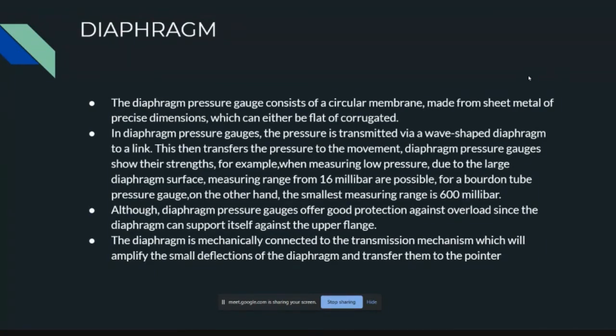Diaphragm pressure gauges show their strength, for example, when measuring low pressure. Due to the large diaphragm surface, measuring ranges from 16 millibar are possible, whereas for a Bourdon tube pressure gauge the smallest measuring range is 600 millibar. Also, diaphragm pressure gauges offer good protection against overload since the diaphragm can support itself against the upper flange. The diaphragm is mechanically connected to the transmission mechanism, which amplifies the smallest deflections of the diaphragm and transfers them to the pointer, to measure the applied force.